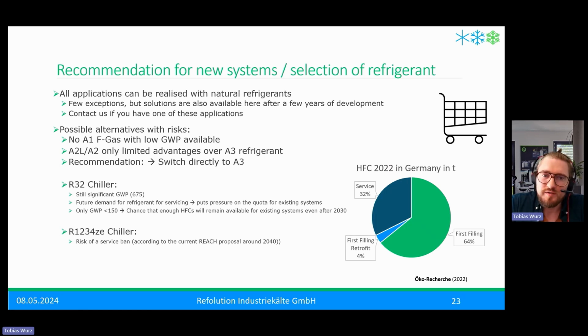So 1/3 was used for service. As I said, for the F-gas regulation, the phase down, in 6 years, we only have 1/6 of refrigerant available. That means first filling will fall down completely, but even for service, you would only have 1/2 of today. So our recommendation is go as low as possible with the GWP, and not only because it's available.